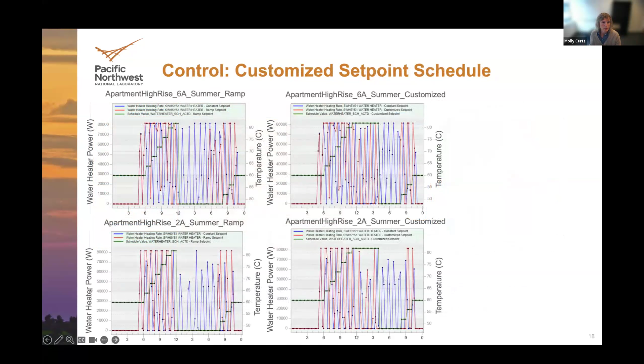We still did find that there were cases where we were getting a higher peak with our control strategy compared to, say, the ramp approach, and that's what we're showing in this graphic. For climate zone 2A, this was the apartment high-rise prototype, and we found that we got less of a reduction using the customized approach compared to the ramp. We had a lower reduction of peak kW, at least for this day that's shown here. But generally speaking, we got a better demand reduction with the customized approach.